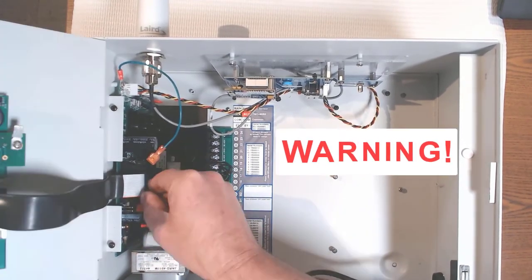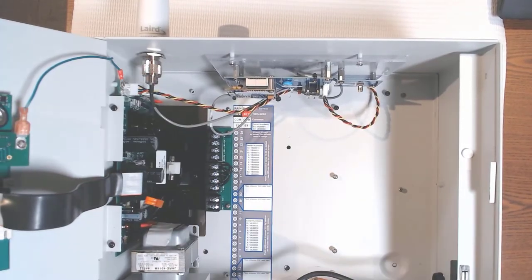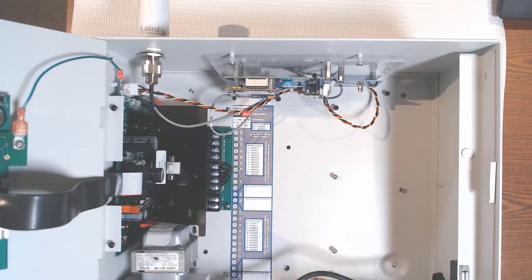With all communication modules, make sure that the antenna is connected before powering up the controller. Connecting a module without an antenna will damage the device and void the warranty.